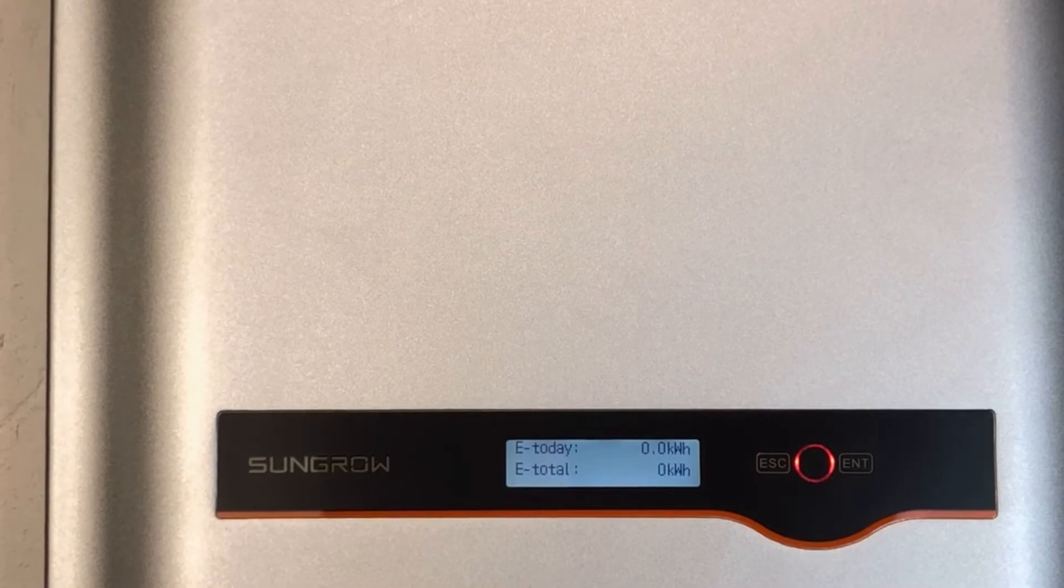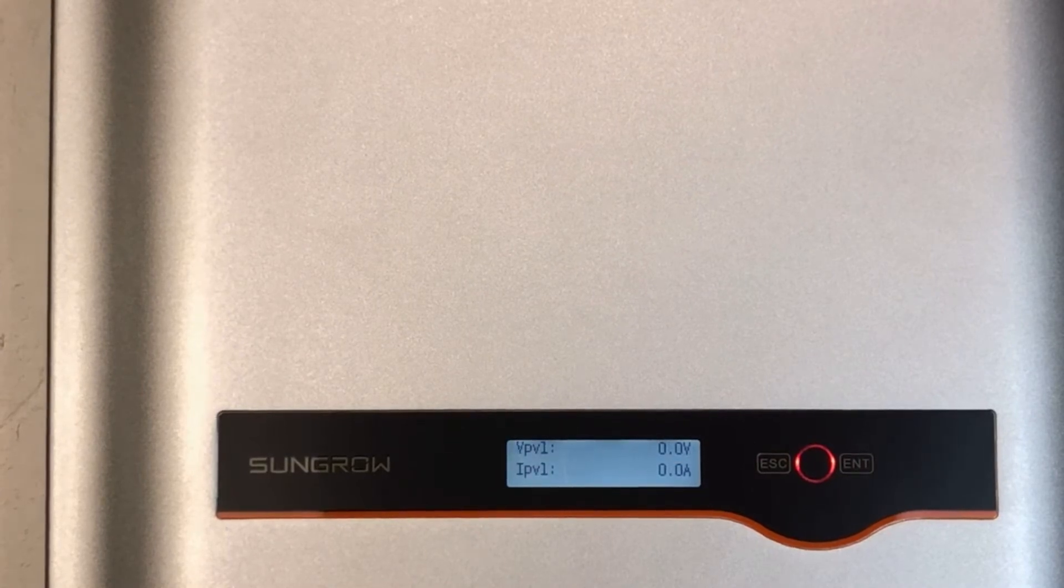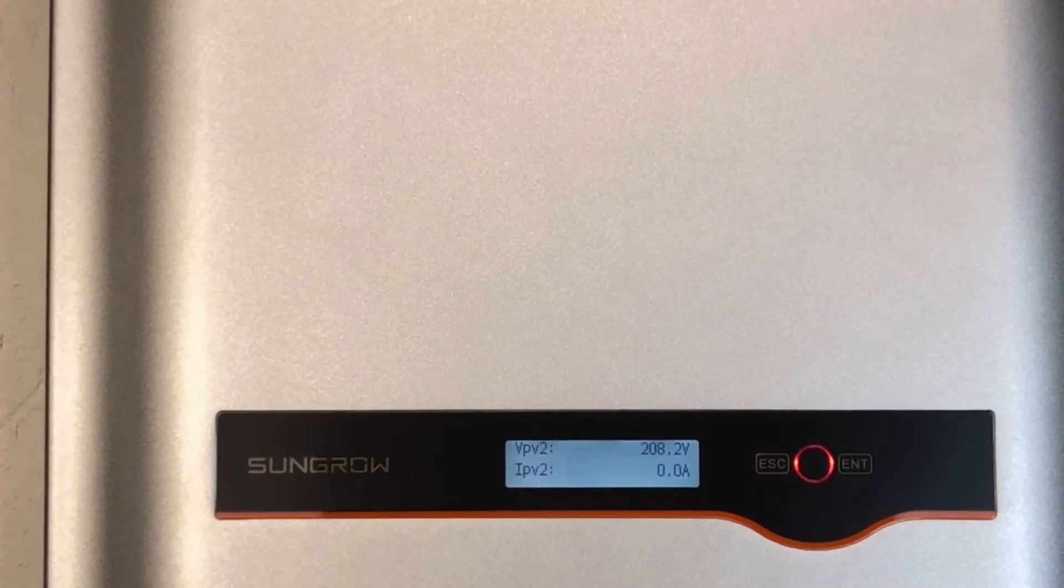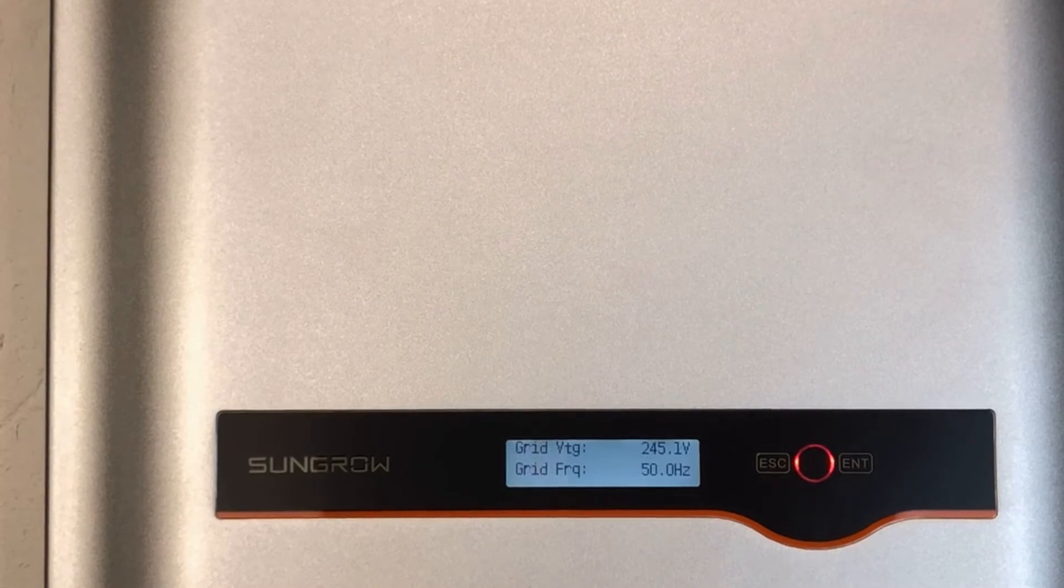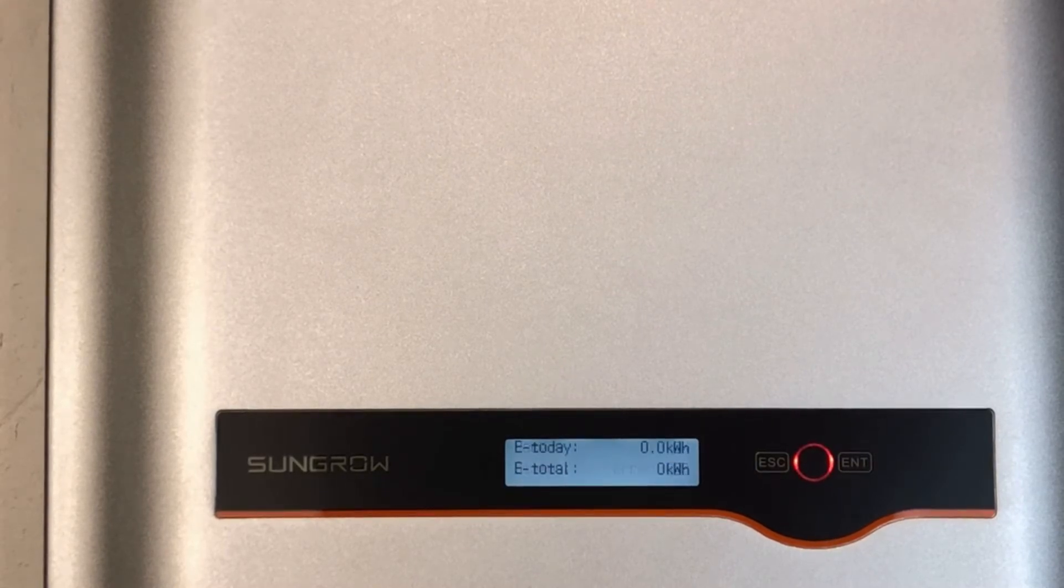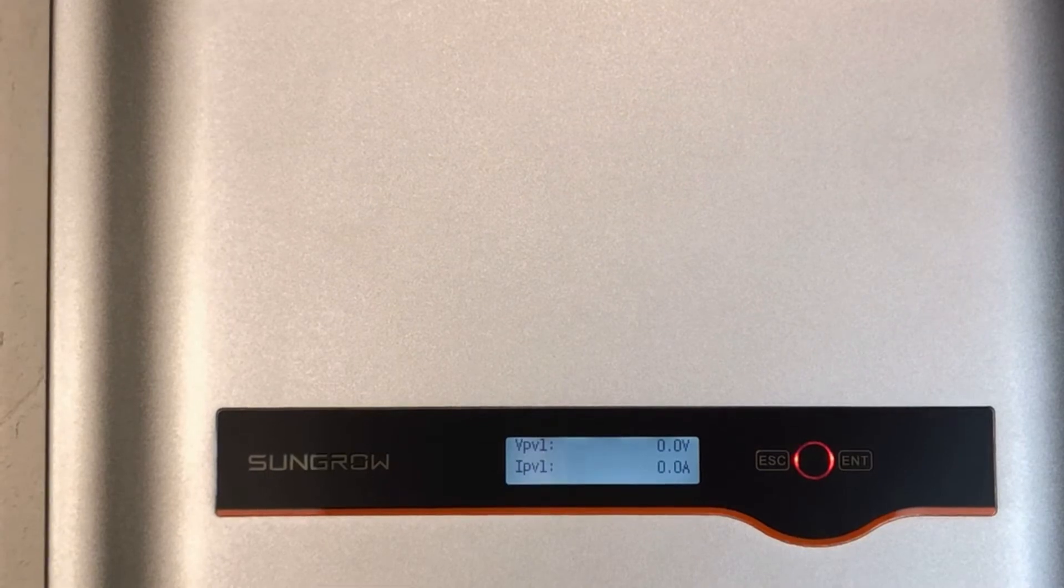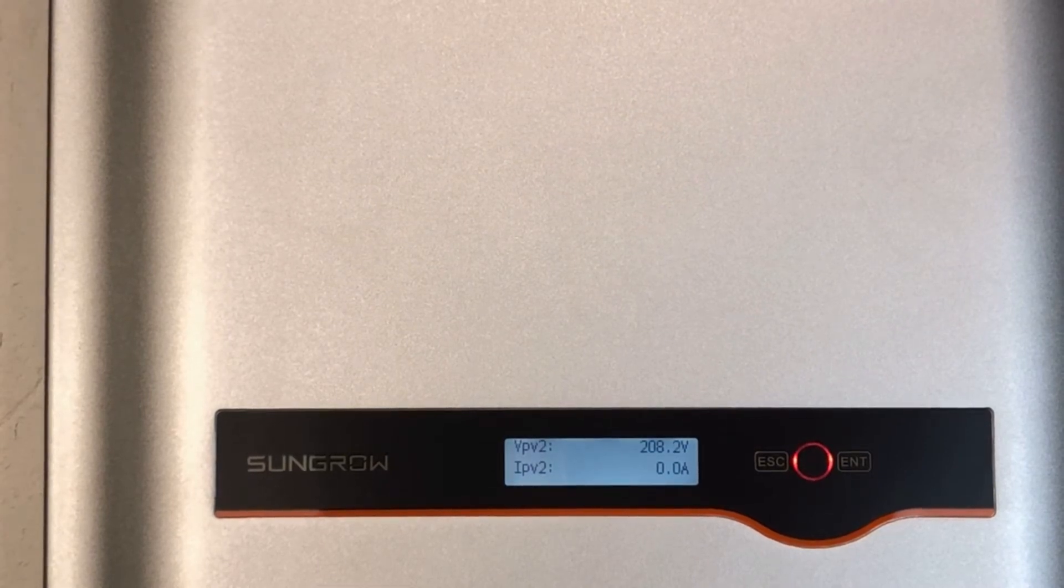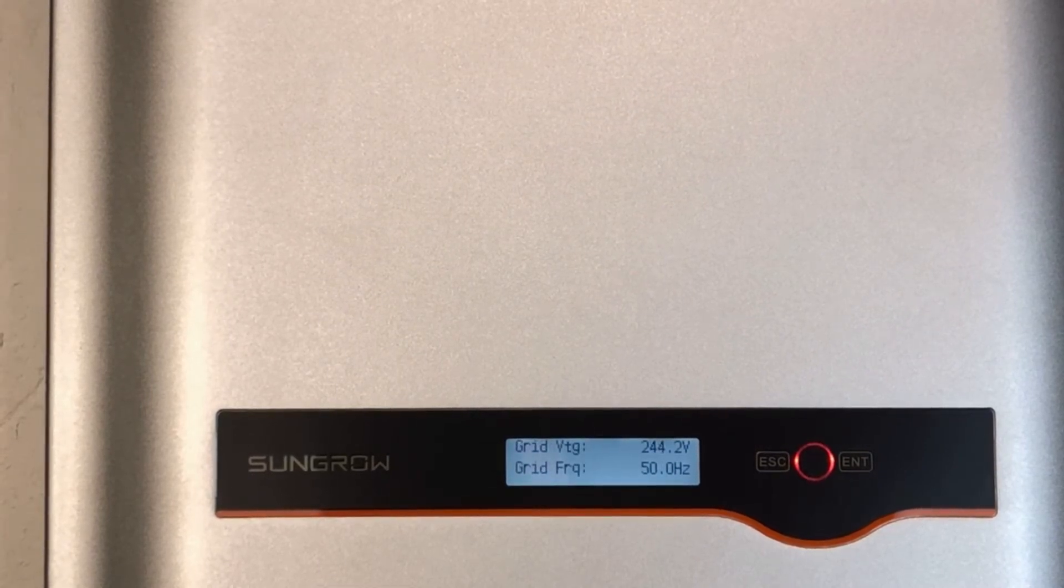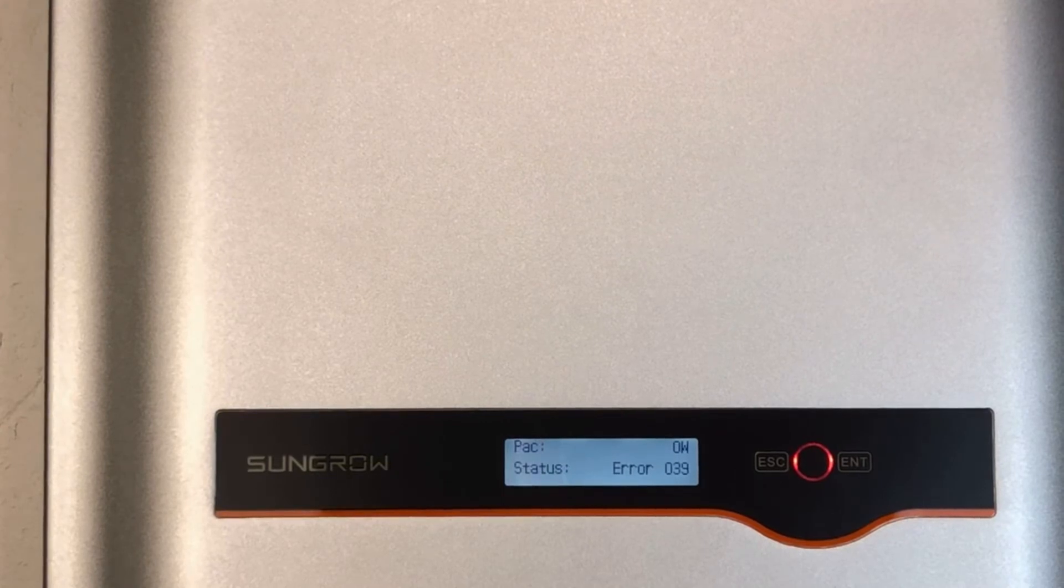So it could potentially be a problem with the solar panels - could be moisture getting into the panel somewhere, could be damage to the cables. We've even seen cables which have been gnawed on by rats or possums. It could be water getting into an isolator or something like this.